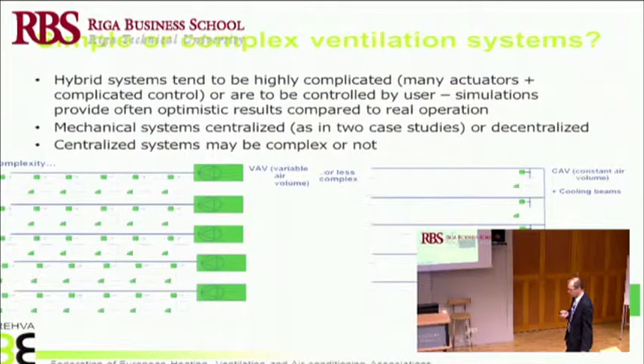As you know, in a cold climate you basically need heat recovery, so you cannot avoid mechanical ventilation, because with mixed or hybrid ventilation, mixed mode as it's called, you are not able to achieve heat recovery effectiveness close to 80% or more, which is needed in our cold climate. So basically you need a mechanical system. You can have another operation mode for the summer period, for example in atriums using window openings or other passive means, but in winter time a mechanical system is basically a must.